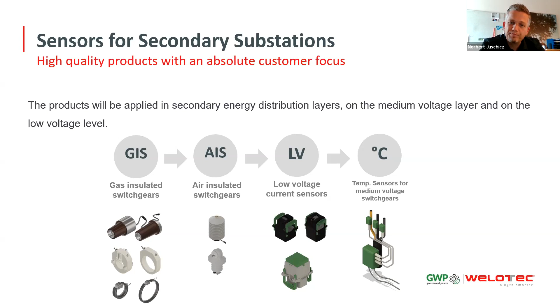Some utility companies are also considering what do we really need? Is it necessary to have low voltage current sensors on the secondary side? Or is it still enough to just put a temperature sensor measurement into the place? The simple reason is the utility companies want to know, do I have an overload there or not? With this information, they can make switching regulations, or they can foresee the lifetime of components inside the ring main units.